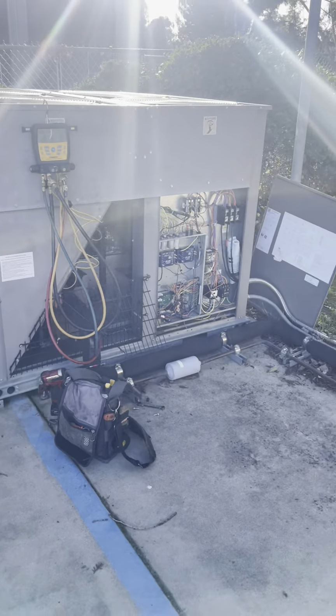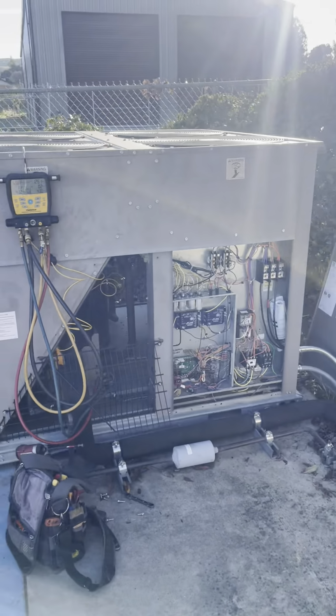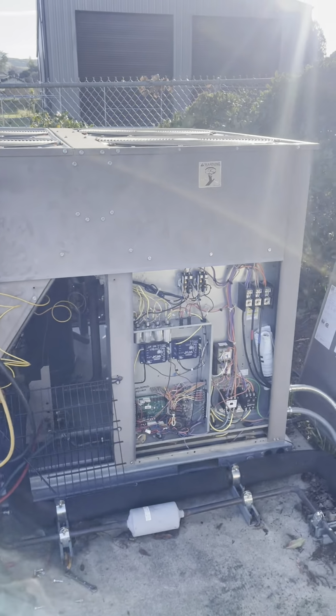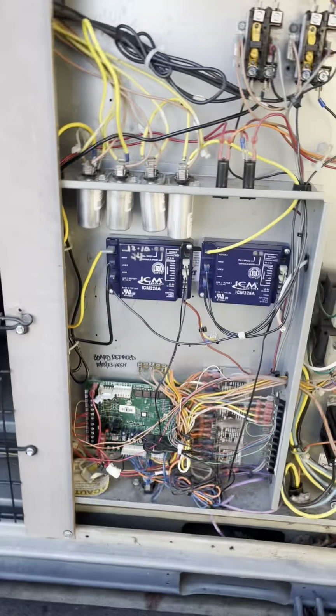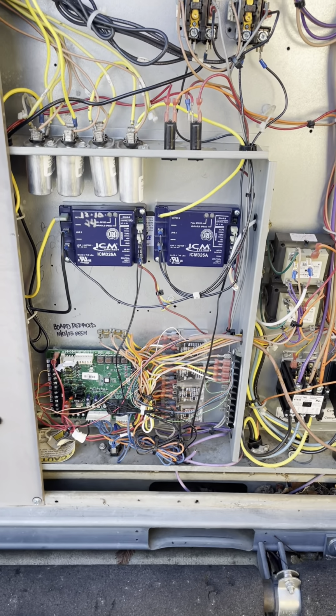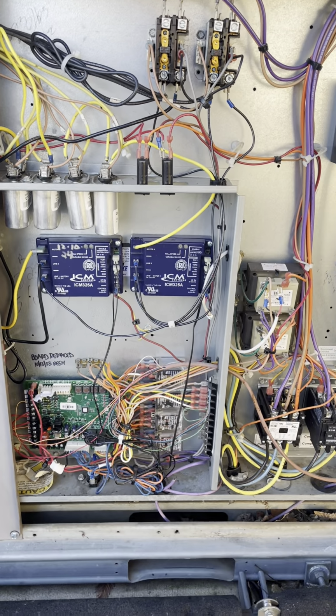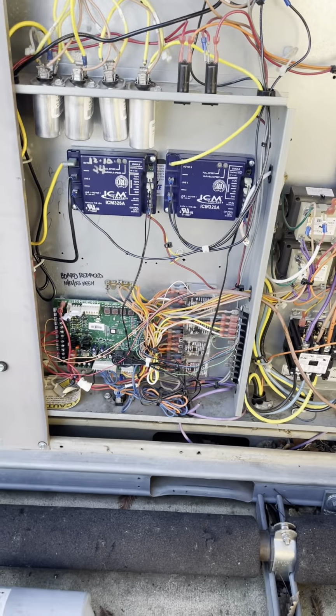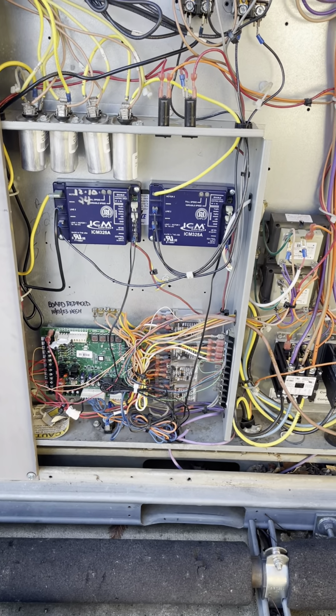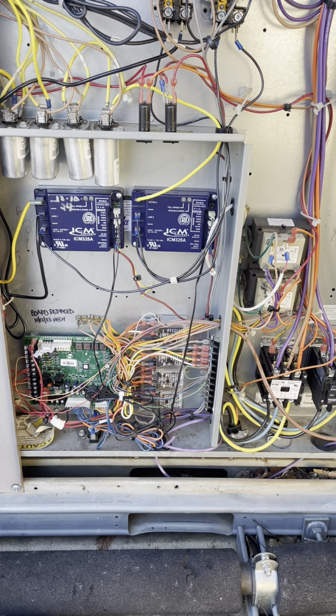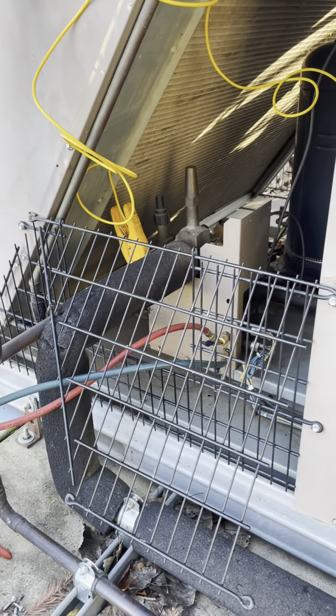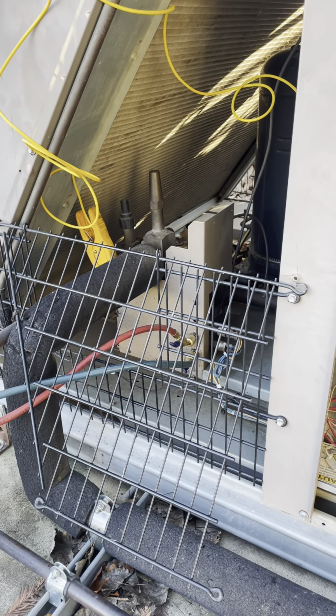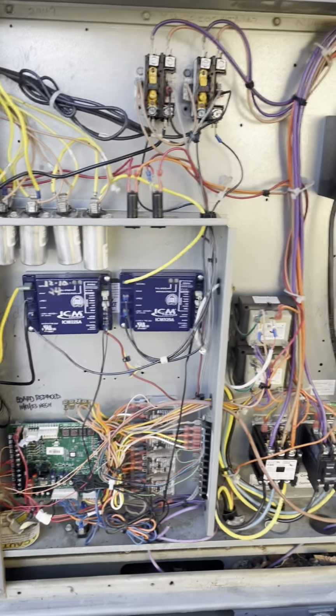Okay, working on this 20-ton York split system here. Customer said that it is not keeping up. We recently just replaced these condenser fan control modules, and we've already replaced the board fairly recently, maybe a year ago or so. So right now I'm probed up to it so that I can check my readings once it's fully staged up and running. I'm not sure what's going on here yet.